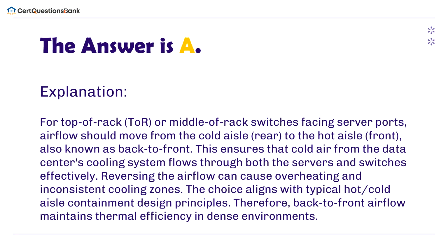The answer is A. For top-of-rack, TOR, or middle-of-rack switches facing server ports, airflow should move from the cold aisle, rear, to the hot aisle, front, also known as back to front.